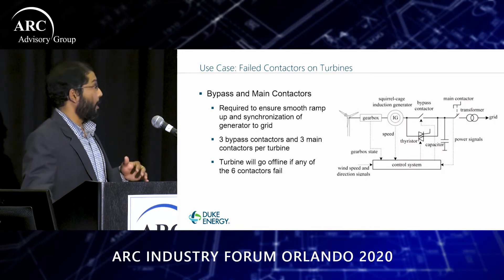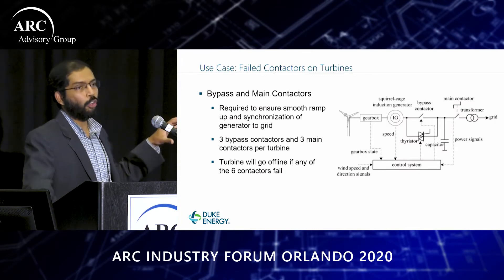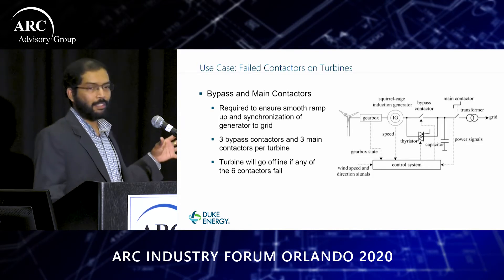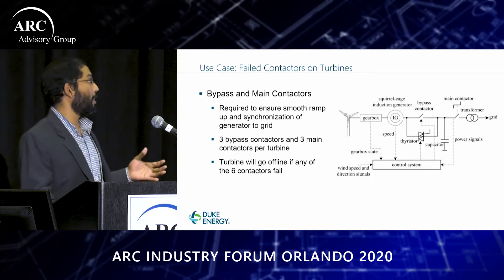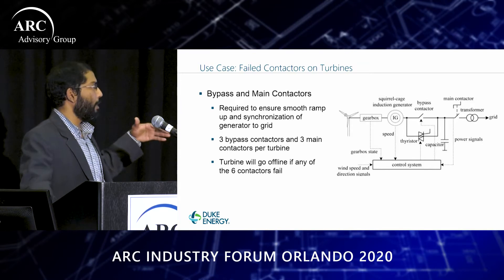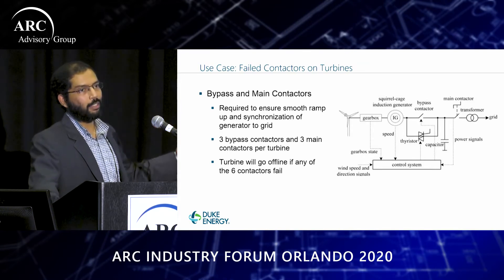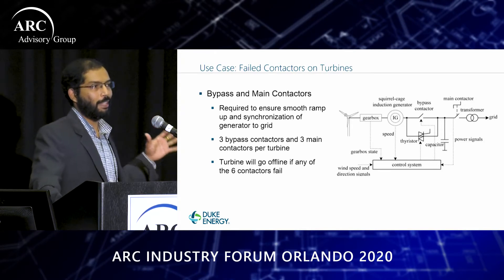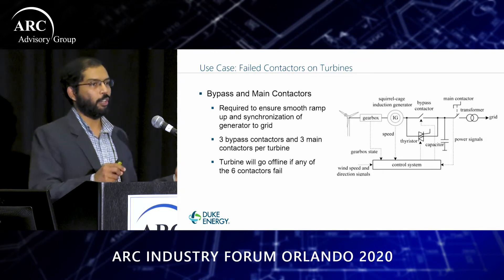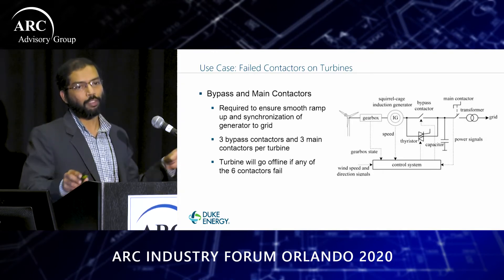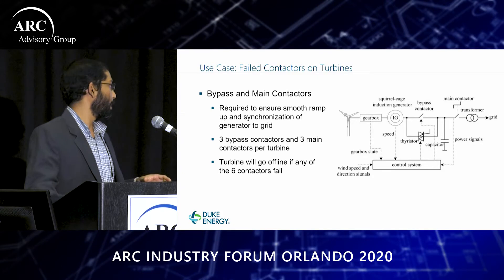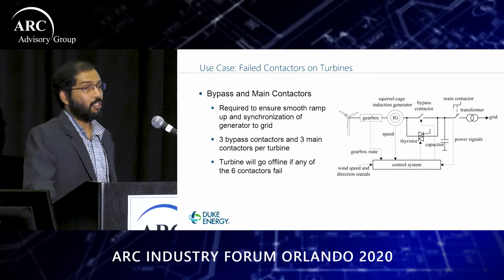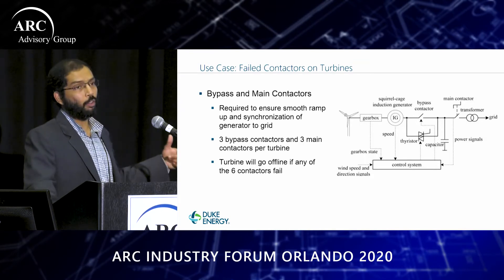For this particular use case, I'll be talking about contactors. These are essentially big relays and there are six of them on each turbine. Their purpose is to make sure that when a generator kicks in it ramps up smoothly and synchronizes with the grid. Certain models of turbines have a design flaw and contactors tend to fail more frequently at one of our sites. A turbine will go offline if any one of the six contactors fail.